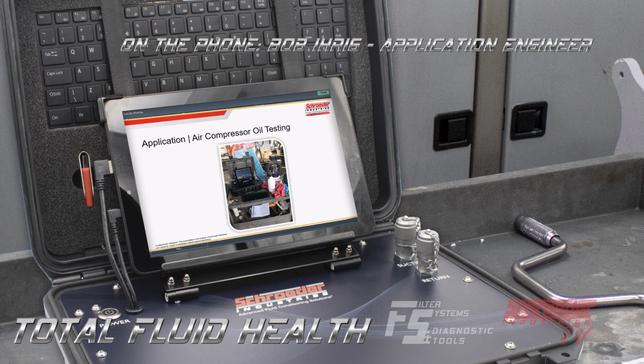For instance, in this air compressor oil testing application opportunity, what we're trying to do is measure the condition of a compressor oil in a piece of machinery over time to see the effect of the increased contamination or the introduced contamination on the fluid condition over time, and really why we can't do this with an FCU, for example, is that air compressors are air compressors, and sometimes the fluid can become very aerated. So it's important that we employ a measurement device that can handle said aeration, and with the air bubble negating capability of the total fluid health unit, it really enables us to apply a portable condition monitoring unit into this type of application.